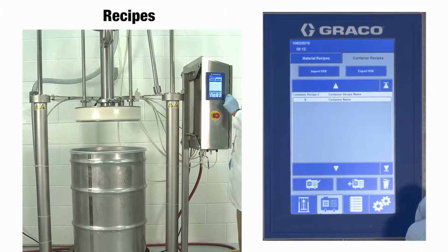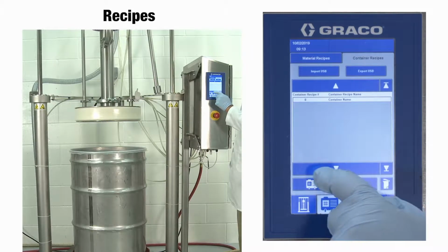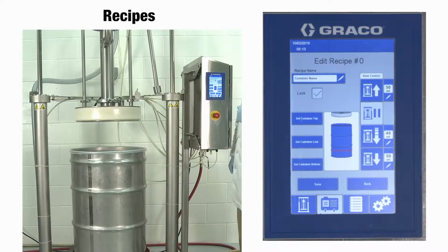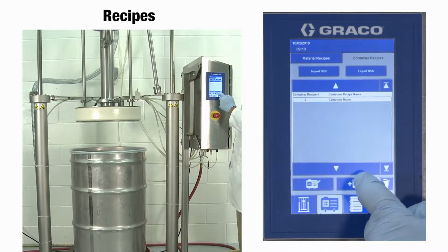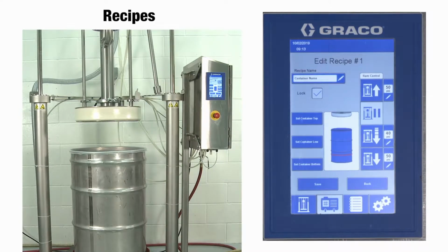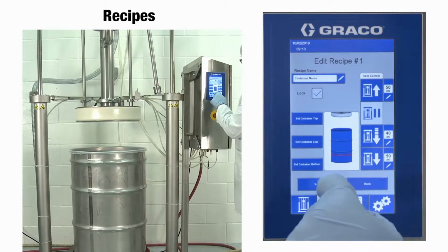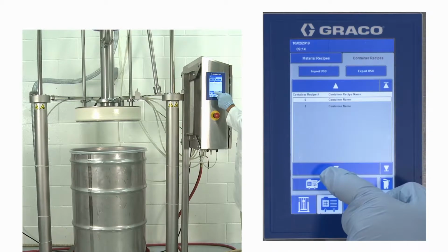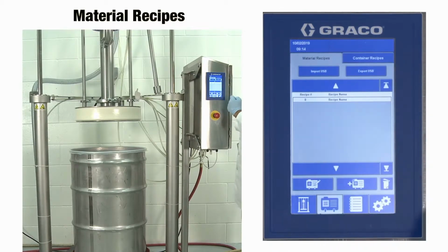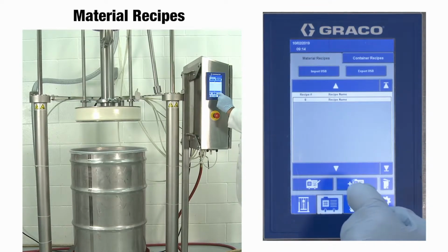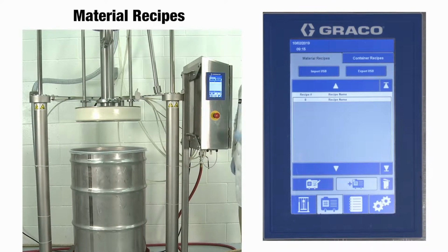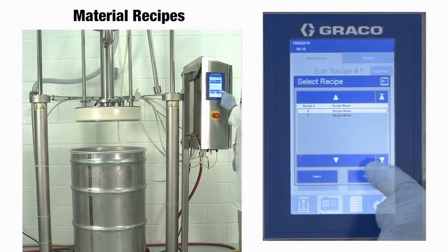When creating a new recipe from scratch, default pressure settings will be pre-filled in. These pressures are offered as good starting points, but most will have to be changed to obtain optimal performance for the specific application. Material recipe screens contain settings based on the material being pumped. All material recipes will need to select a container recipe which defines the design of the drum.